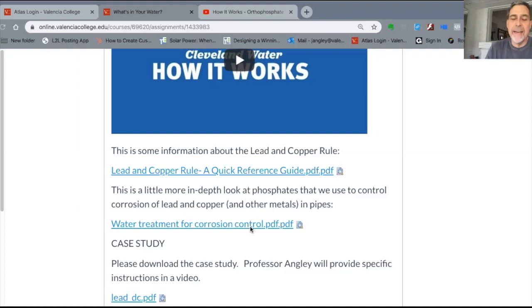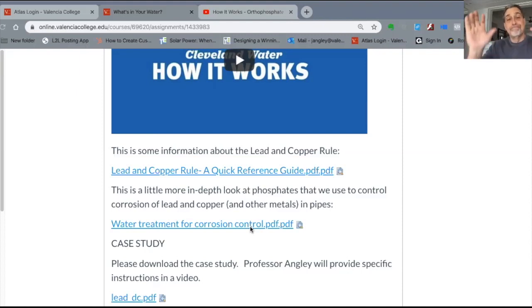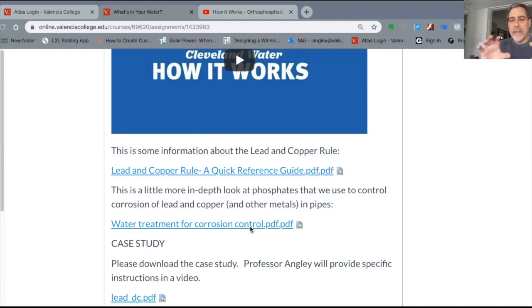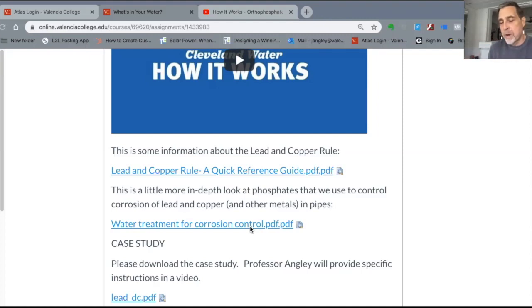Lead is not water-soluble on its own — if you take a hunk of metal and put it in water, it won't dissolve. But as it corrodes or rusts, the oxidized metal can dissolve into the water. So what we want to do is keep the water away from the lead. We do that by coating the inside of the pipe with something like polyphosphate, phosphate, or orthophosphate. That coating keeps the water away from the metal surface, and that's one of the basic ways we control corrosion.